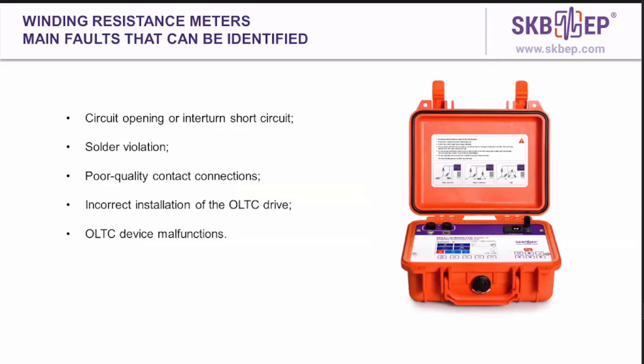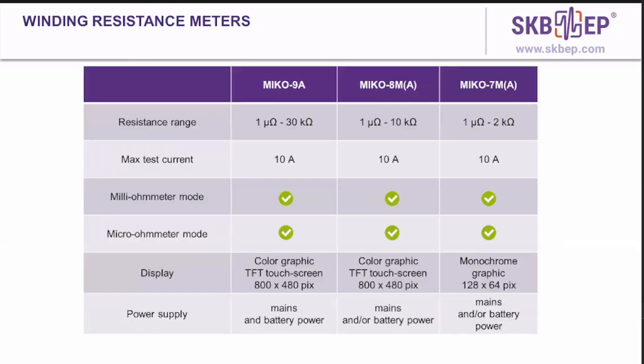Main faults that can be identified by these instruments: circuit opening or interturn short circuit, solder violation, poor quality contact connections, incorrect installation of the OLTC drive, OLTC device malfunctions. Main difference is in resistance range or the upper limit. MIKO 9 up to 30 kilo ohm, MIKO 8 up to 10 kilo ohm, and MIKO 7 up to 2 kilo ohm. Another difference is in the display. As you can see, MIKO 9 and MIKO 8 have big colored graphic touchscreen, while MIKO 7 has small monochrome graphic display. And the power supply, MIKO 9 always goes with battery, while MIKO 7 or MIKO 8 come with or without battery. It's up to the user.